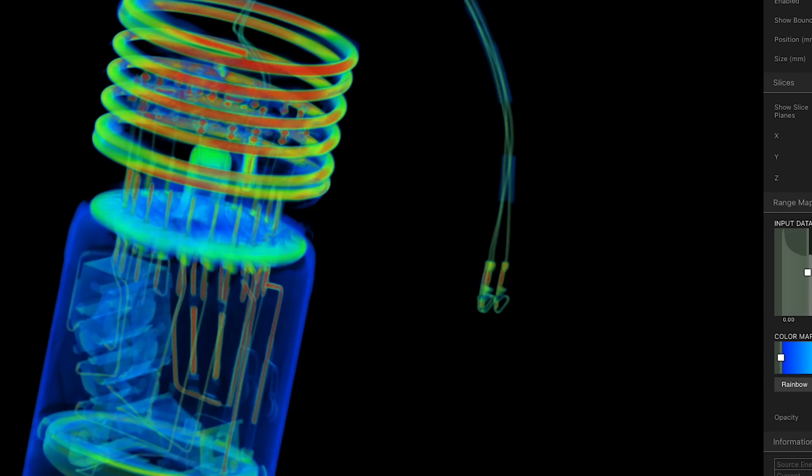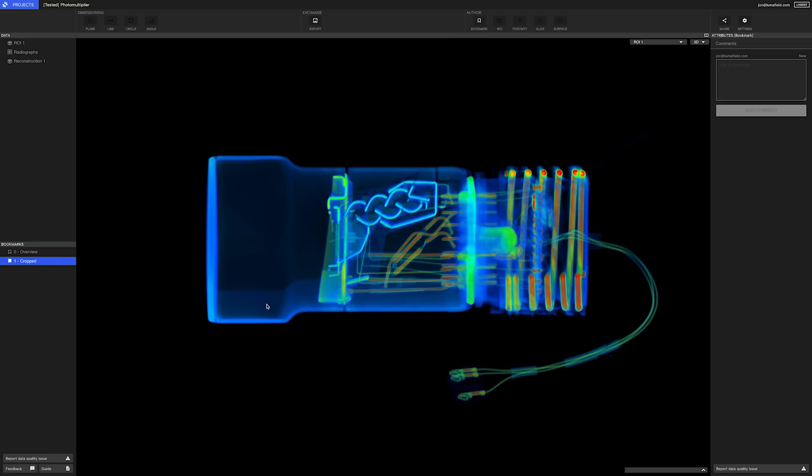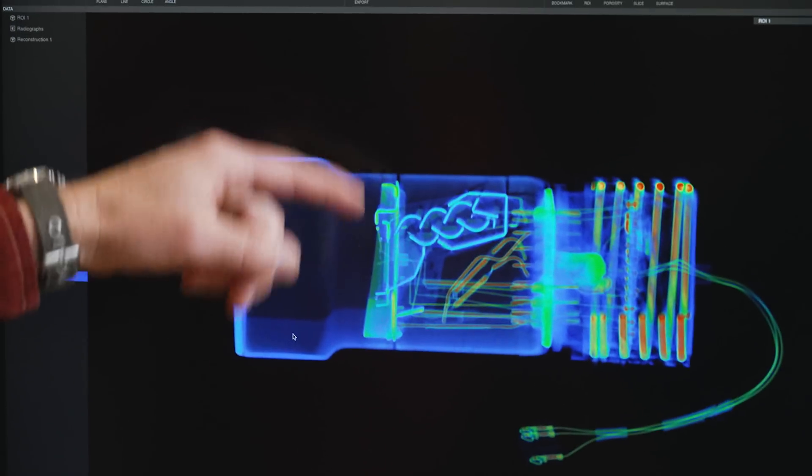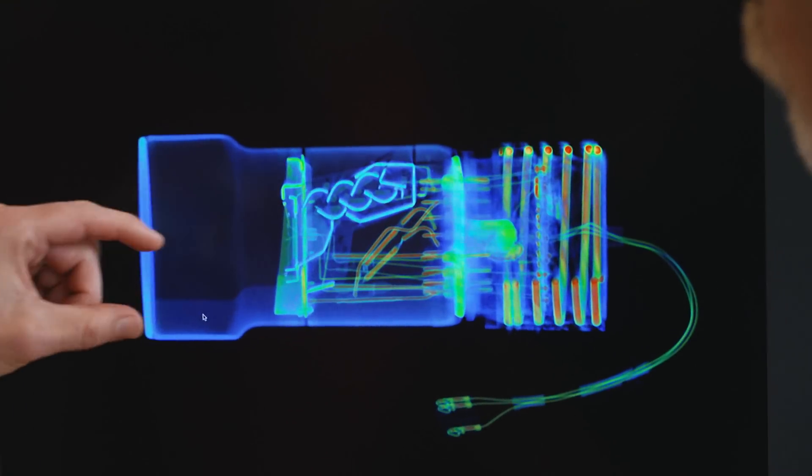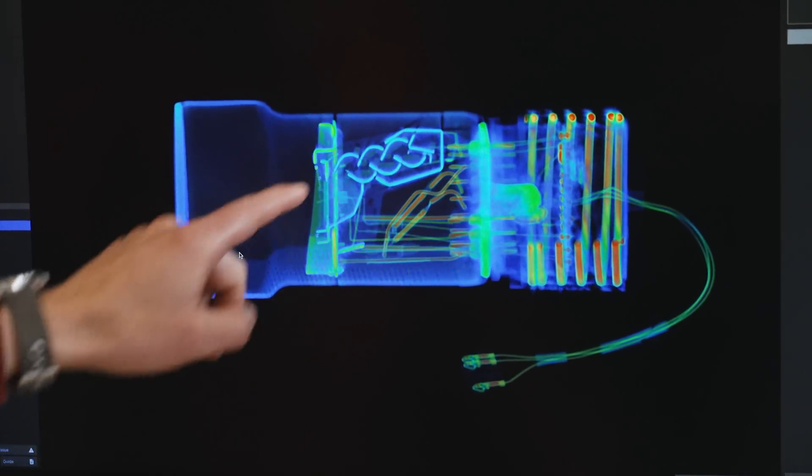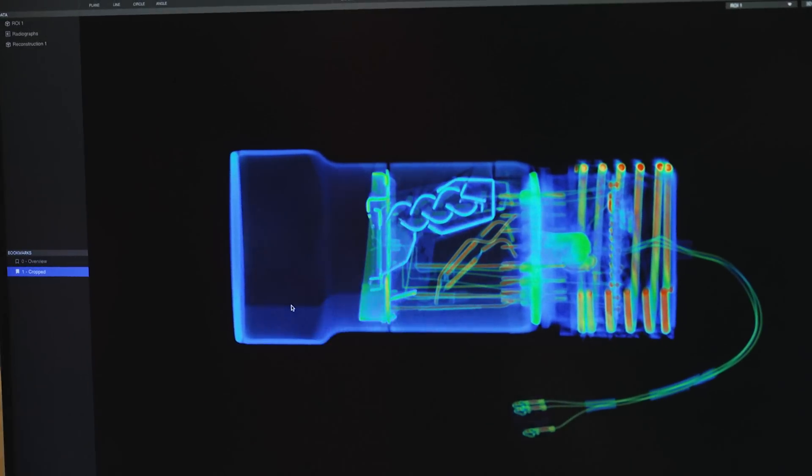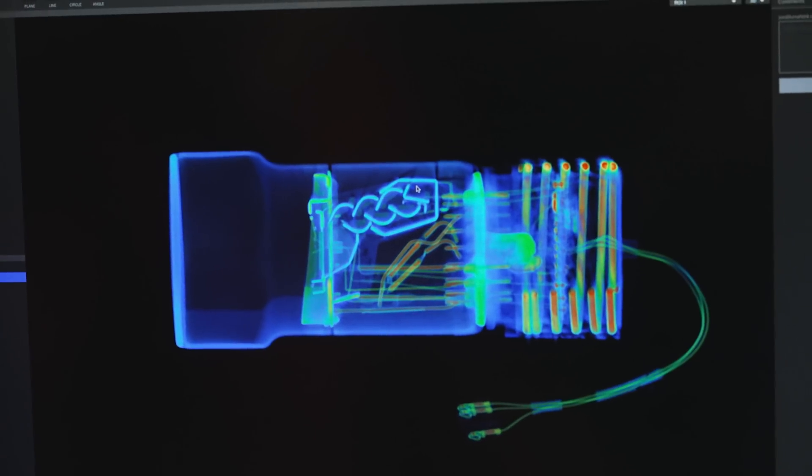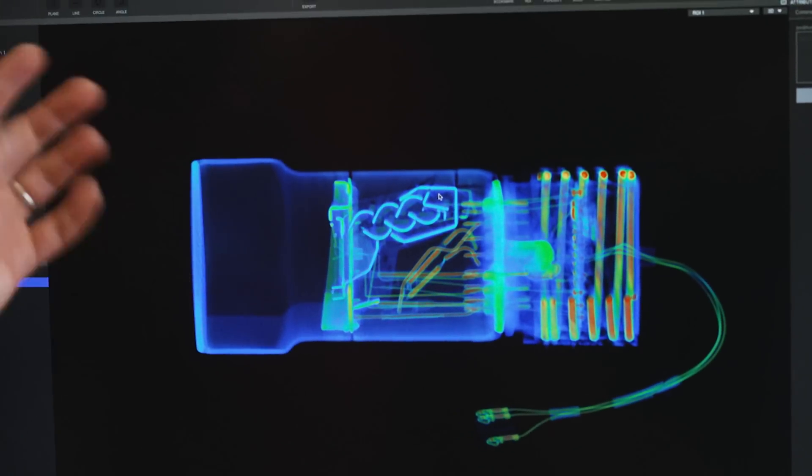Okay, so is it possible to explain how this works by looking at its structure here? Yeah, let's take a look. Actually I've cropped a view here that I think helps better explain what's going on. Now if you look at the real tube, you can't really see all of this just from sight, but you can sort of see the beginnings of these curved pieces of metal here, and that's this kind of strange pathway. You start to realize there's a lot going on here - this is a very artisanally crafted device. What's really cool - what's happening here - photons come in through this window at the end here and they strike a cathode. When they hit that cathode, the photon gets changed into an electron, and that electron gets steered by some electrodes into this first curved paddle here. That paddle is called a dinode. That's right, and there's a whole sequence of these things. This is where the magic happens, and this is why we call it a photomultiplier.